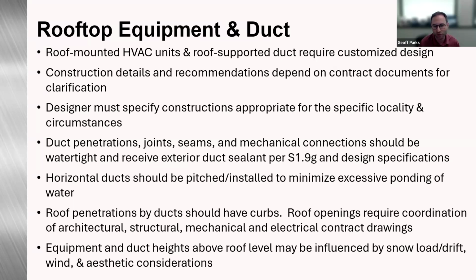Horizontal ducts should be pitched or installed to minimize excessive ponding of water. This especially holds true on very wide, large roof duct that's uninsulated or doesn't have any lagging, that has that pitched or sloped roof to prevent that. Roof penetrations by duct should have curbs. And then roof openings obviously require coordination with the architectural, structural, mechanical, and electrical contract drawings.